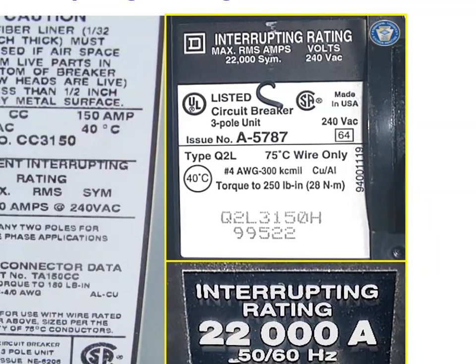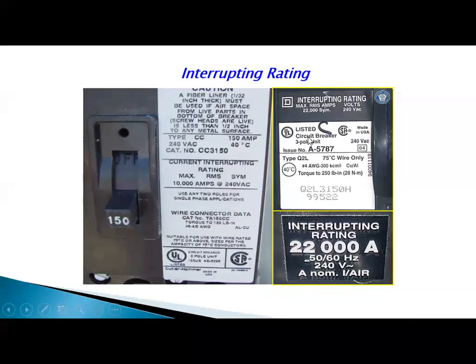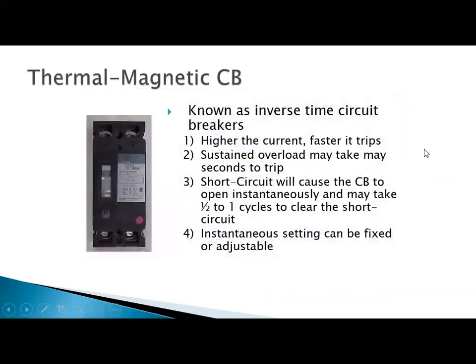And so this would be used on a system that was 240 volts. I have to use at least 75 degrees Celsius wire. It can be copper or aluminum. There is a torque setting on this breaker that I have to make sure I adhere to. And they tell me the size of my wire can be anywhere from number 4 up to 300 kcmil. But the interrupting rating on this one, 22,000 amps. So very important that we know that interrupting rating so that we can eliminate some of these explosions that we want to stay away from.